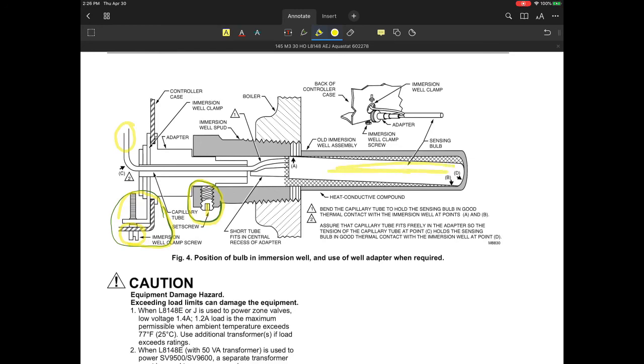The other thing that's going on in here is this set screw that you see right here. When this becomes loosened, that little set screw will allow you to pull the entire sensing bulb out of the well, and it'll allow you to back that whole thing out and replace the Aquastat in its entirety. The well, you shouldn't have to take that out. Part of the reason for having a well is that you don't want to have to take that out if you can help it. They also are talking about, in this particular sensing well, using a heat conductive compound.